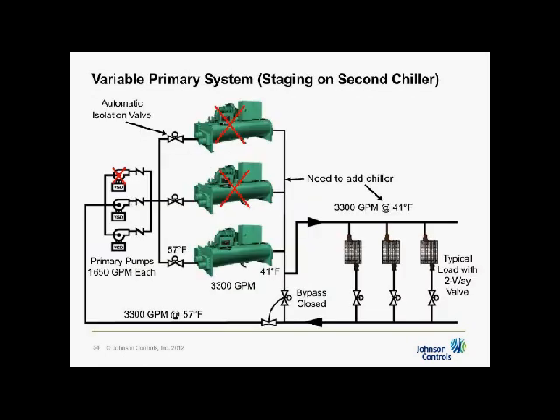Here's an example where I have this chiller at the bottom running. It doesn't matter how many pumps I've got running. I could run two, I could run one. It's up to my algorithm, however I want to do that, because they're headered and they're variable speed, so I can do it any way I like. But over here, this chiller is the only one running, the one I'm pointing to. I want to add this chiller. Whatever the conditions are, in this case, my flow has started to increase, and I'm going above, so my chilled water temperature is starting to rise.